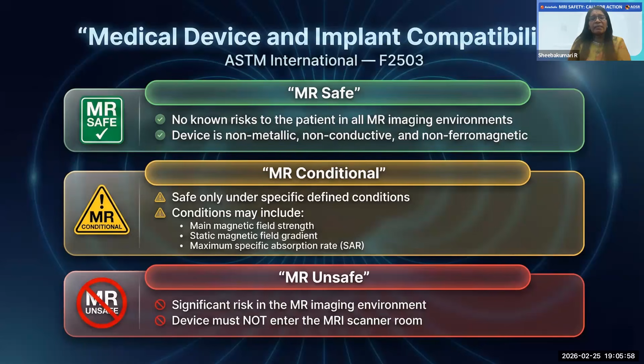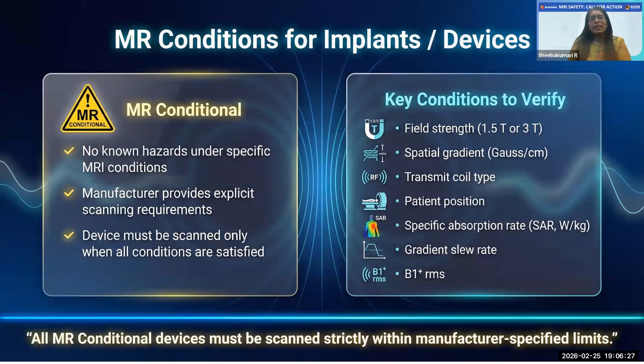The key conditions to verify are: confirm the field strength, the spatial gradient, the transmit coil type, patient position, the specific absorption rate, the gradient slew rate, and the B1 plus RMS condition. The device must be scanned only when all the scanning conditions are met. With partial compliance, we should not do the implant scanning.